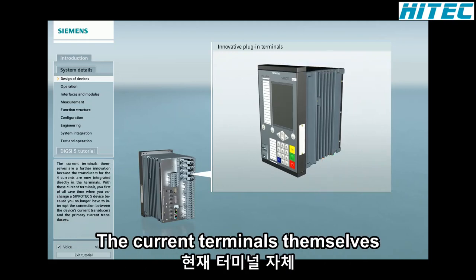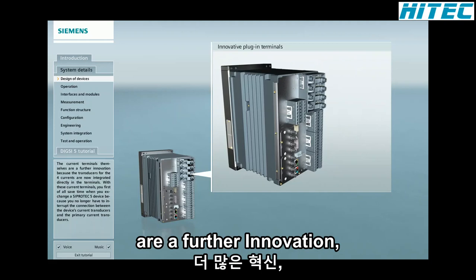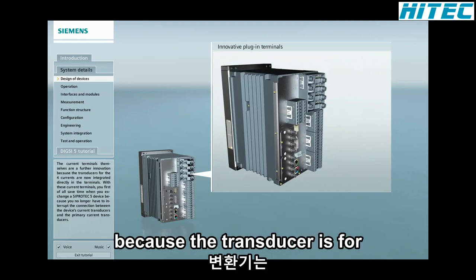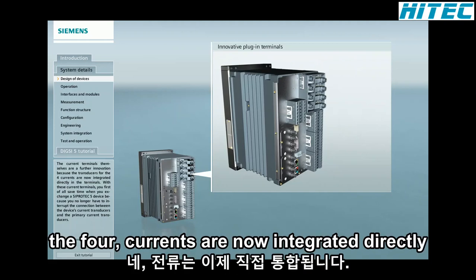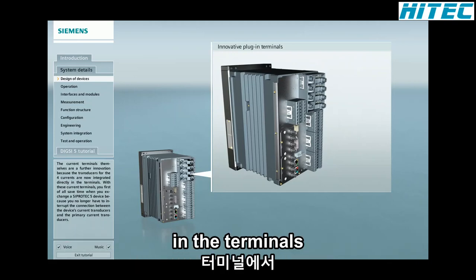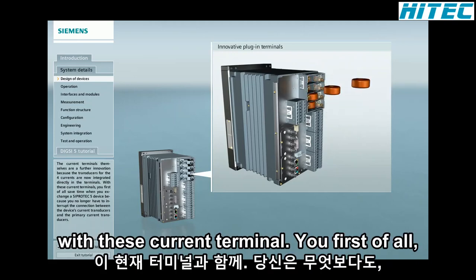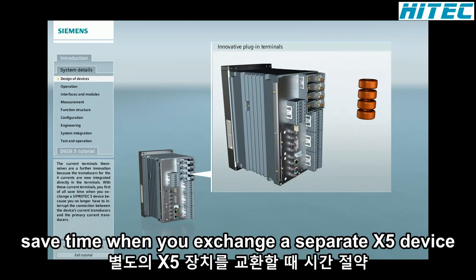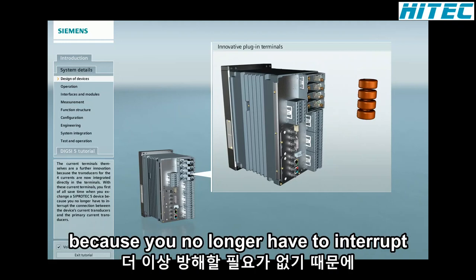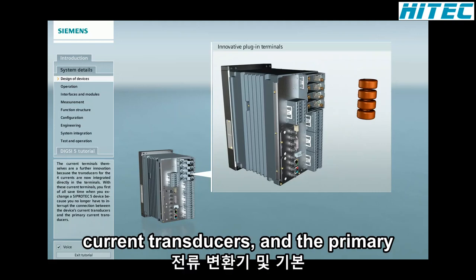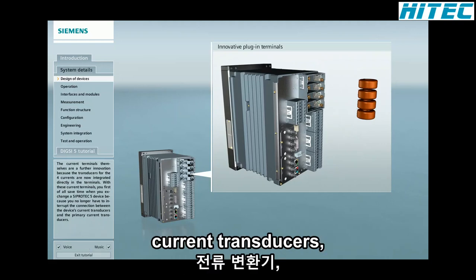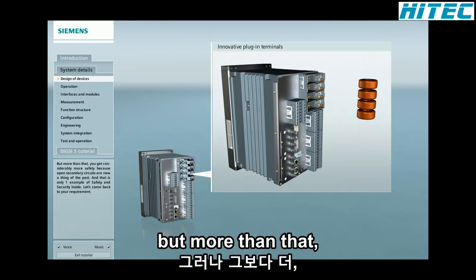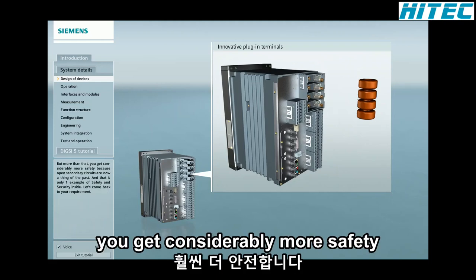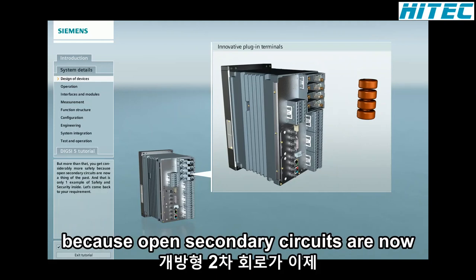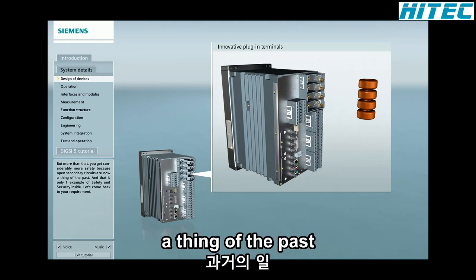The positive side effect of this intelligent assembly solution: wiring errors are practically impossible when you exchange a device. The current terminals themselves are a further innovation because the transducers for the 4 currents are now integrated directly in the terminals. With these current terminals, you first of all save time when you exchange a SIPROTEC 5 device because you no longer have to interrupt the connection between the device's current transducers and the primary current transducers. But more than that, you get considerably more safety because open secondary circuits are now a thing of the past.